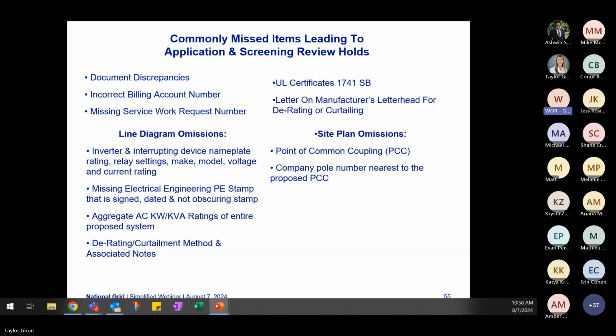There are some commonly missed items leading to application and screening review holds. I'll focus on line diagram and site plan omissions. For line diagrams: inverter and interrupting device nameplate rating, relay settings, make, model, voltage and current rating, as well as a missing electrical engineering PE stamp that is signed, dated, and not obscured. Also aggregate AC kW ratings of the entire proposed system, and derating or curtailment method and associated notes. For site plans: point of common coupling labeling, and the company pole number nearest to the proposed PCC.